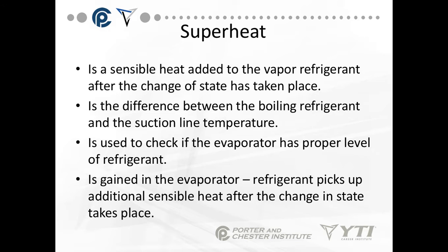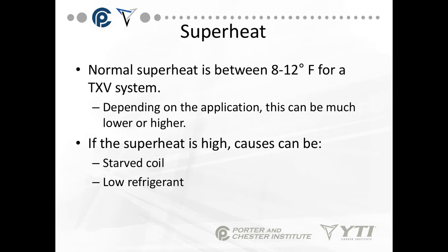Superheat goes along with the evaporator, which is why we're talking about it in this lesson. Superheat is a sensible heat that's added to the vapor refrigerant after a change of state has taken place. It's the difference between the boiling refrigerant and the suction line temperature, and it's used to check if the evaporator has a proper level of refrigerant. Superheat is gained in the evaporator as refrigerant picks up additional sensible heat after the change of state from liquid to vapor. Normal superheat for a TXV system is between 8 and 12 degrees.